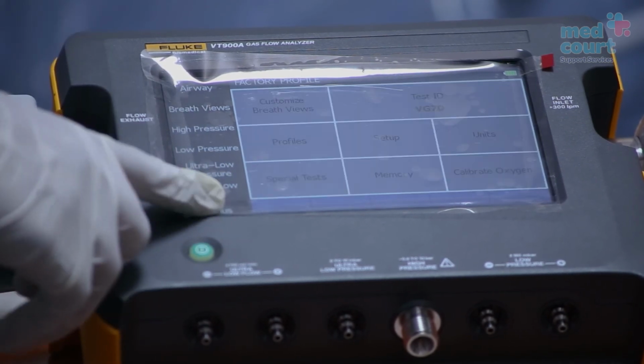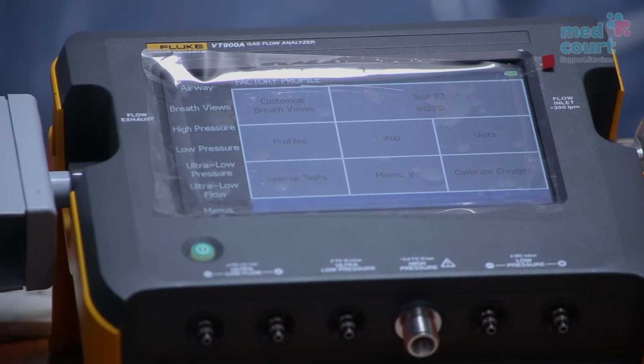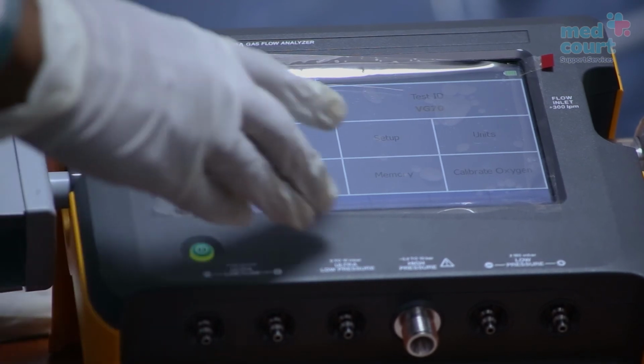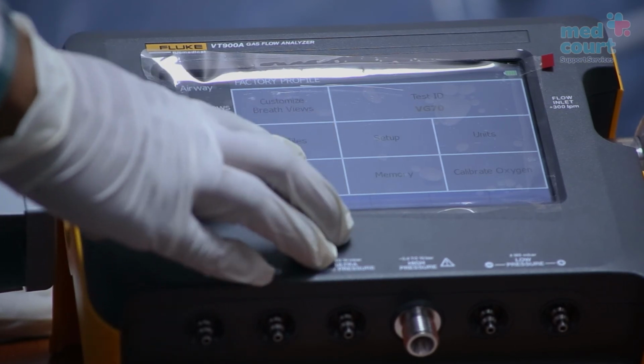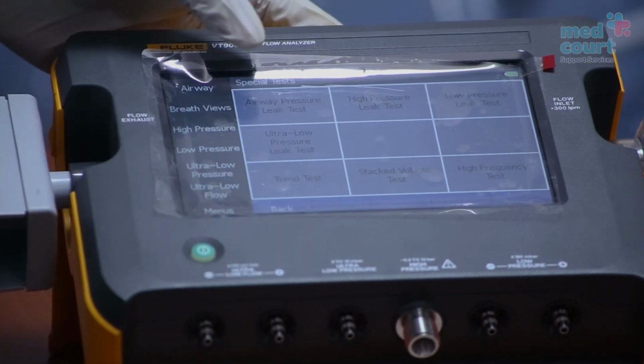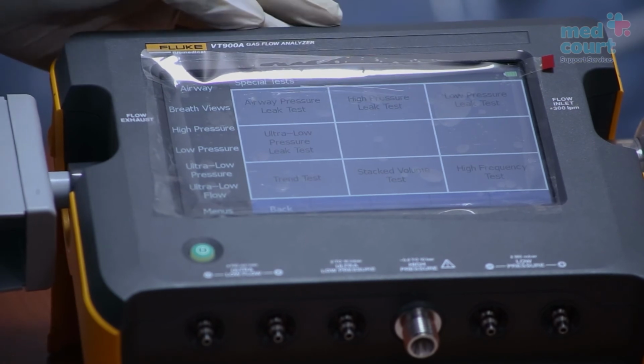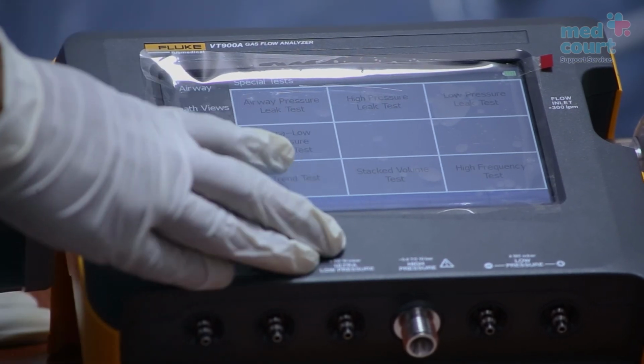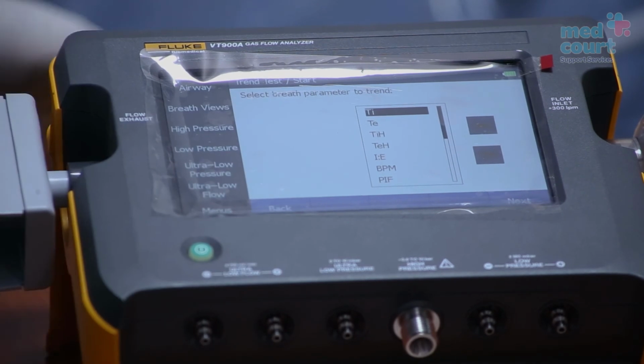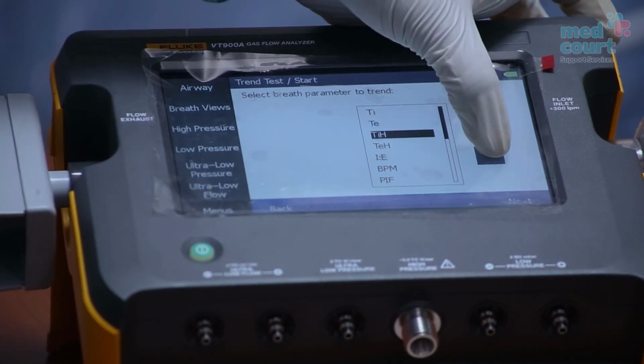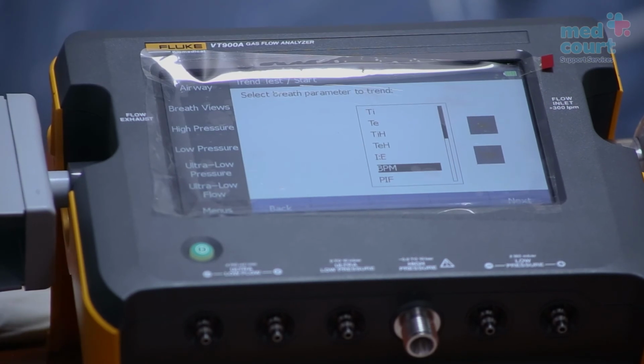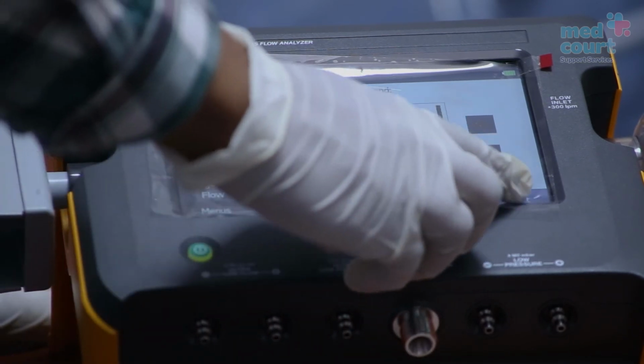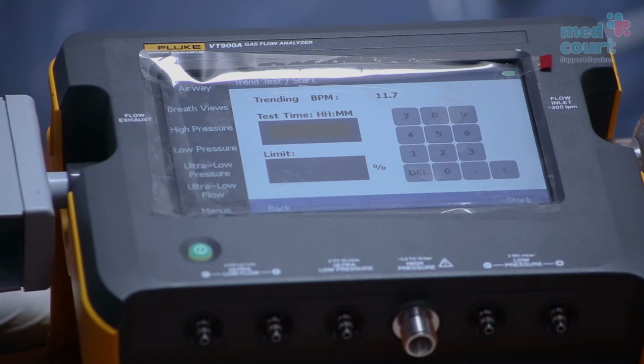On the menus option, there is an additional section for special tests. Click Menus, Special Tests. There are various options to select. The trend test, for instance, allows you to pick a particular parameter to check for on the ventilator. For instance, we'll be picking the BPM, which is breaths per minute. Click Next. Input a test time and a limit and start.